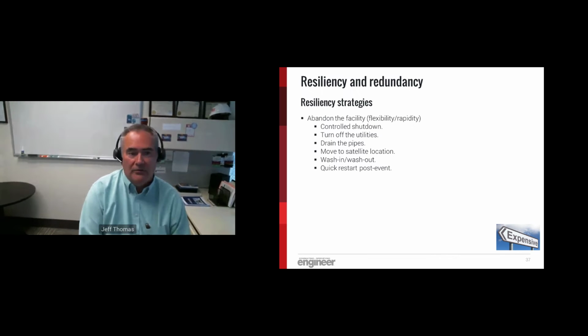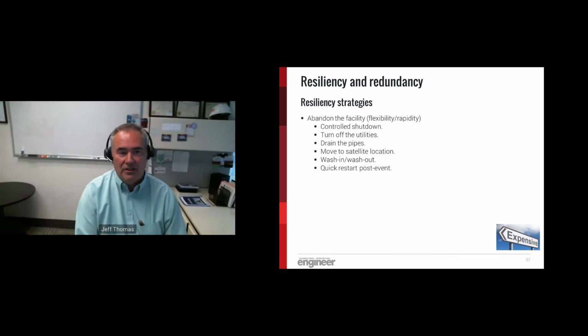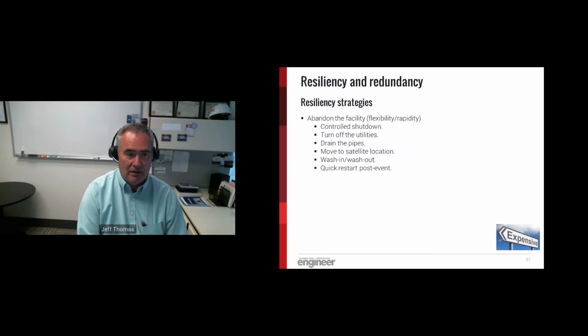On the other end, what if we just abandoned the facility and ran away until the event was over and then came back? It's a perfectly valid strategy. Those of us in Houston during the February Snowmageddon event, that's what a lot of us did. We shut off the water to our houses and we drained the pipes and we left. And then when the weather warmed back up, we came back. Quick restart is key to that. And our electrical systems can be designed to support that as well.